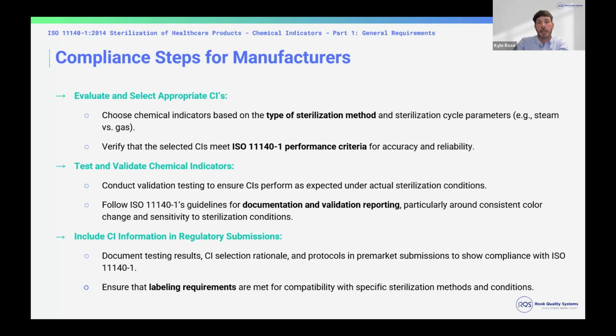Verifying that they meet the performance criteria for the ISO 11140 for accuracy and reliability. That also ties back to actual batch controls and things like that as well. So making sure that when you receive, if you're doing this sterilization in-house, you receive the certificates of compliance, assurance, whatever, with these new chemical indicators that you're doing. If you're reviewing your sterilization for your vendors, also make sure that they are keeping this information for their chemical indicators. Conducting validation testing to make sure they perform as expected under the actual sterilization conditions, and then following guidelines for documentation and validation on the chemical indicators. In some situations, you might have to include this in regulatory submissions, or it's more likely it'll be covered during an audit as well and review of sterilization.